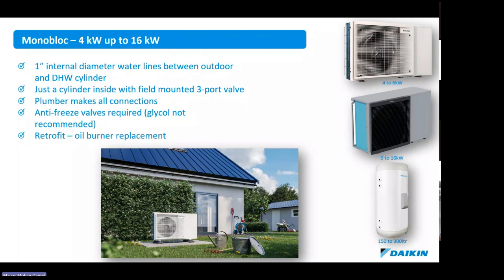The thing is, you have a little bit more flexibility on the cylinders, so you can have any size cylinder you want, from 100 litres up to 500, 1,000 litre if you want, depending on the size and capacity of the unit. One of the other big advantages is the fact that you don't need F-gas. So the connection, as I said, in the refrigerant split in our last slide, that connection must be done by an F-gas or refrigerant engineer because plumbers wouldn't have the bottles or gauges or anything to do that. But with water, this is a straightforward water connection and they can do that.